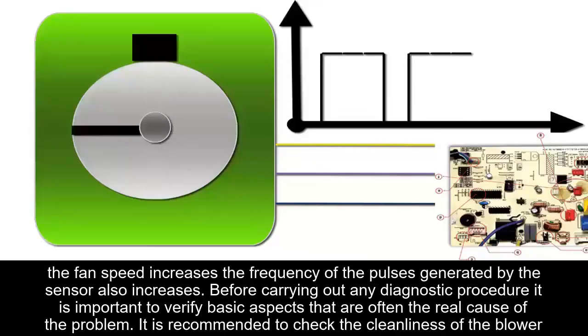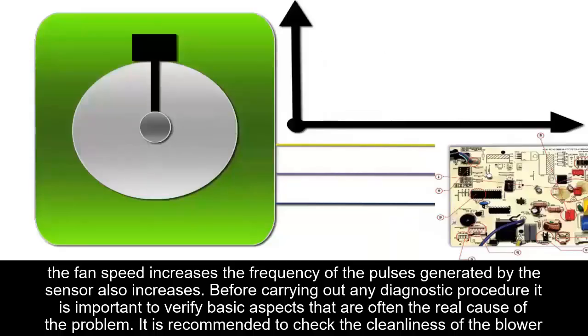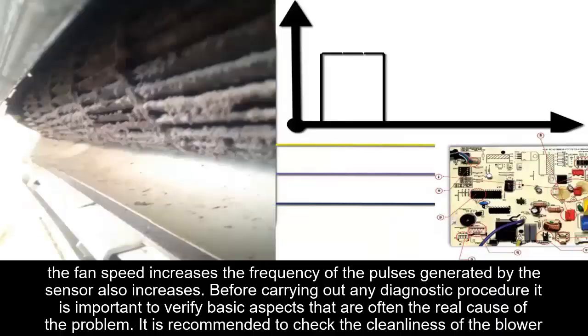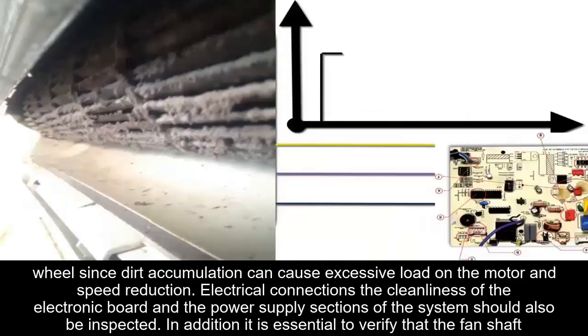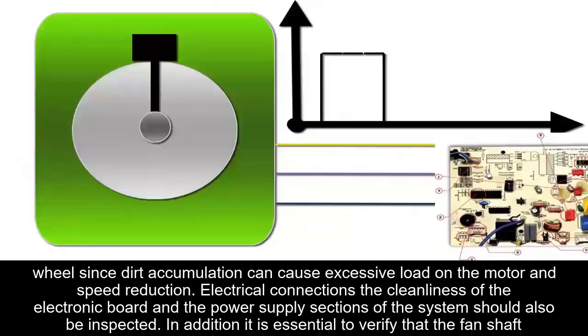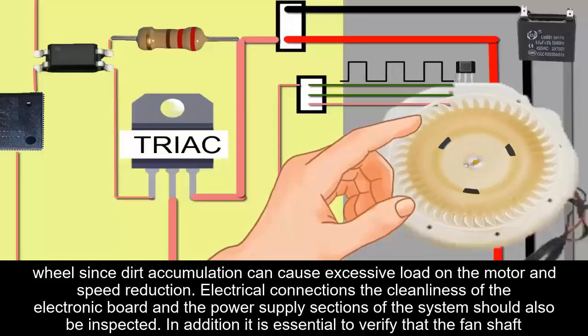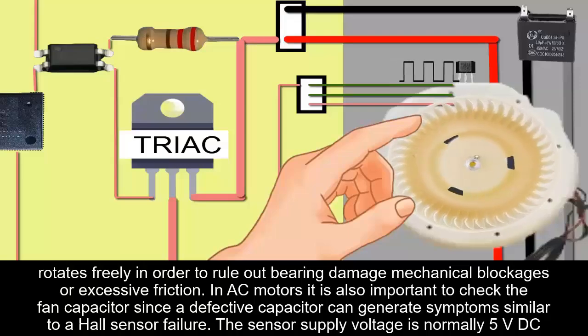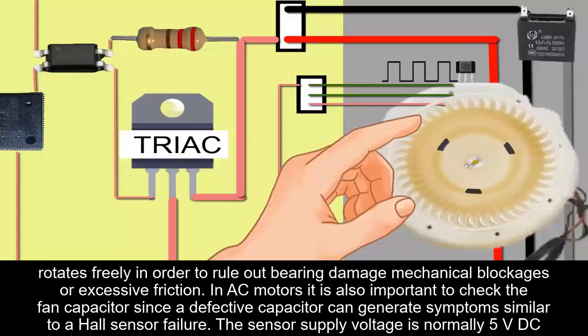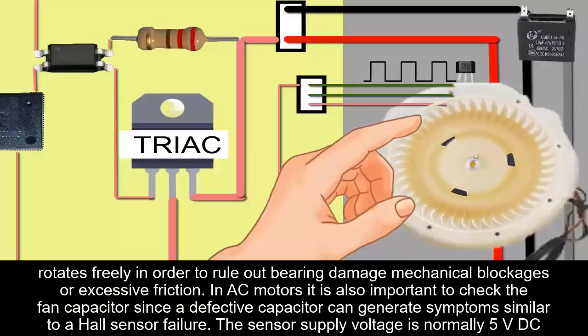Before carrying out any diagnostic procedure, it is important to verify basic aspects that are often the real cause of the problem. It is recommended to check the cleanliness of the blower wheel, since dirt accumulation can cause excessive load on the motor and speed reduction. Electrical connections, the cleanliness of the electronic board, and the power supply sections of the system should also be inspected. In addition, it is essential to verify that the fan shaft rotates freely in order to rule out bearing damage, mechanical blockages, or excessive friction.